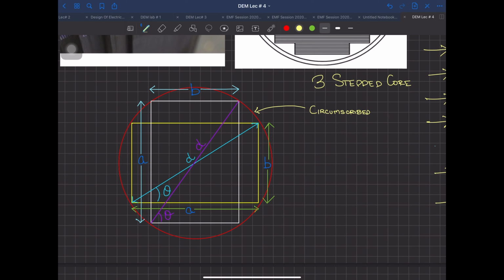Whenever you are going to draw a winding on it, you are not going to start the winding directly on this without any cylinder. Why? Because if you have the edges pointed out together, that will cut the wire. When this transformer is loaded or short circuited, in any case, there will be forces exerted on the winding, maybe compression or maybe outward.